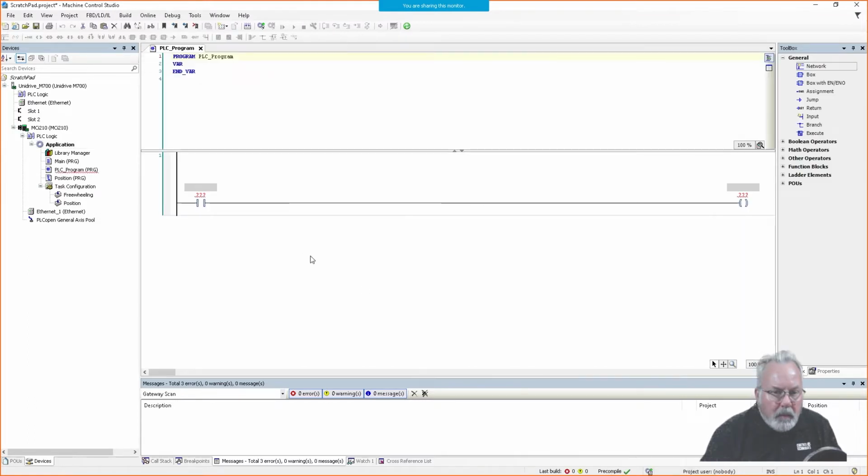And I should also point out, one of the common questions that I get is, can't I change the development language once I have declared a POU? The answer to that is no. Once you have declared a POU, you can't go in and change the development language. You would need to delete the POU and then recreate it using the language that you would like to use. So now I have 3 POUs.